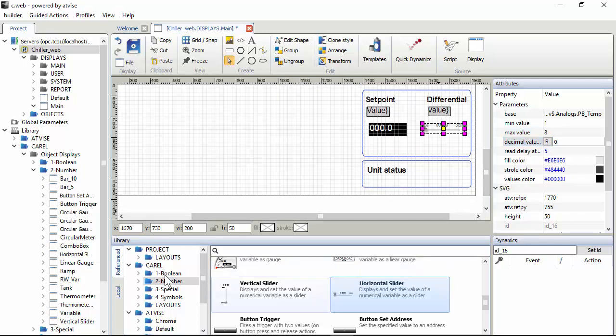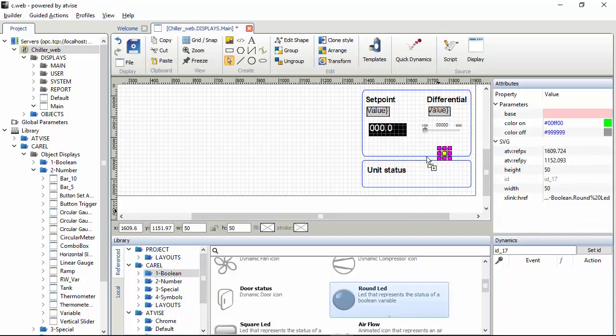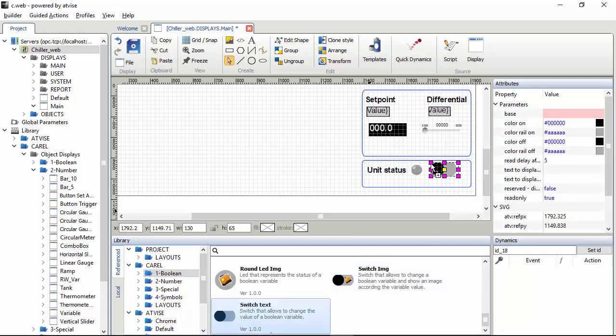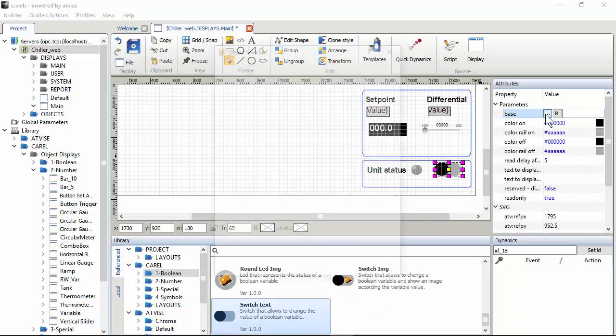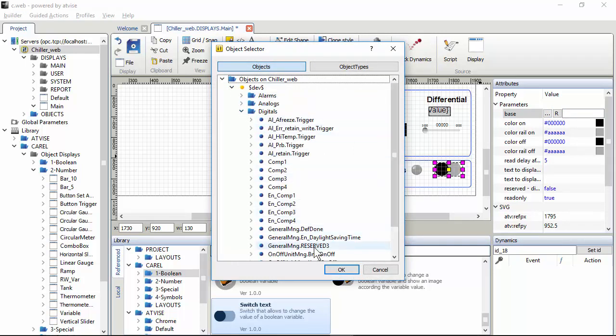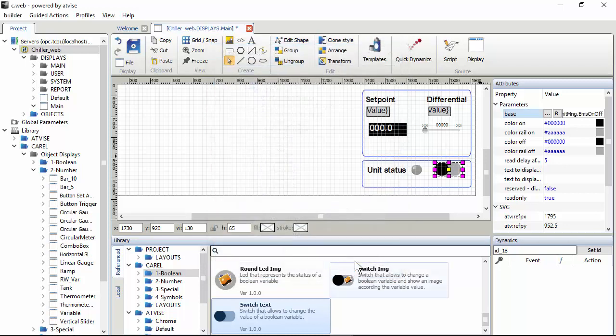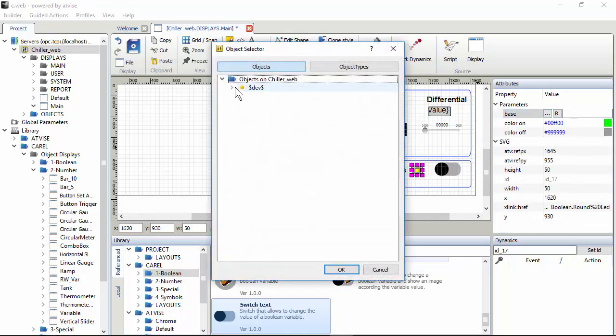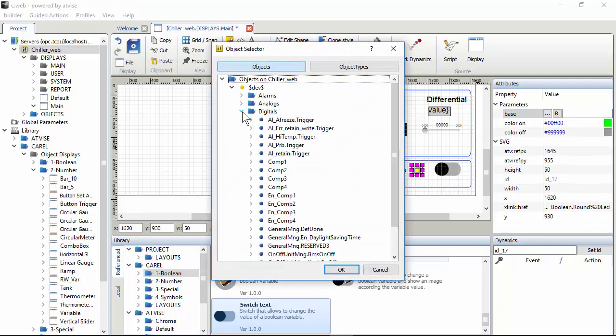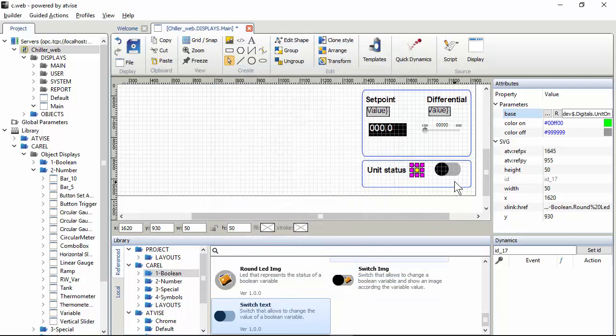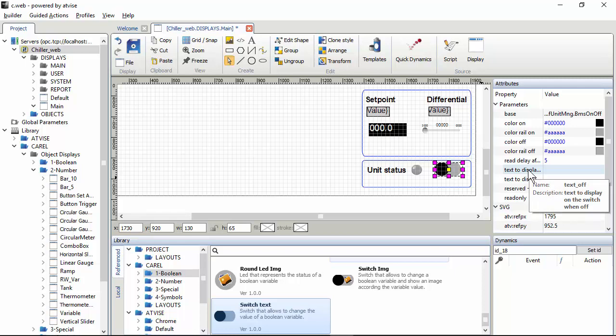For the unit status, we can place a boolean round LED and a switch text. For both, for this, the variable is the on-off. There is the BMS on-off. While for this is unit on-off. The application running in the controllers has these variables, so I will use the same. This is a switch text, where we can define the text to show when the value is 0 and 1 or false and true.